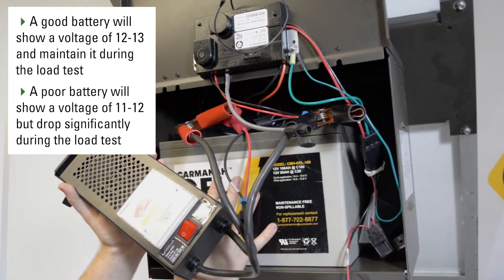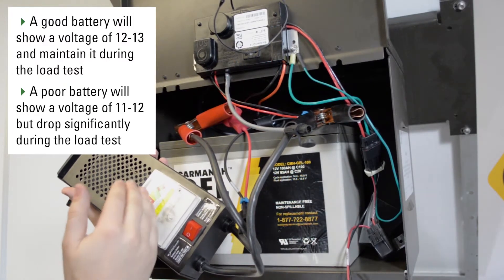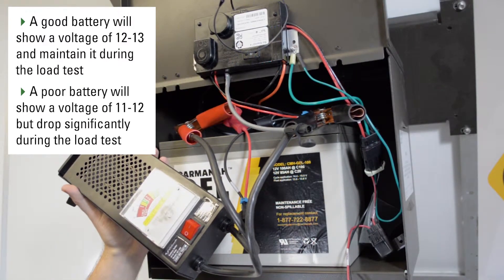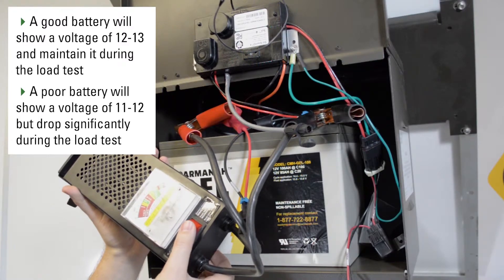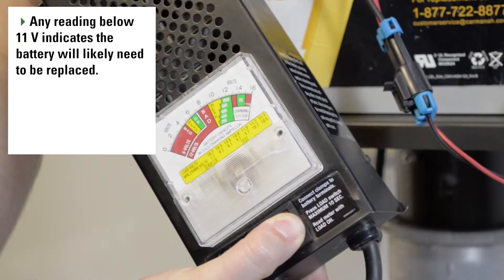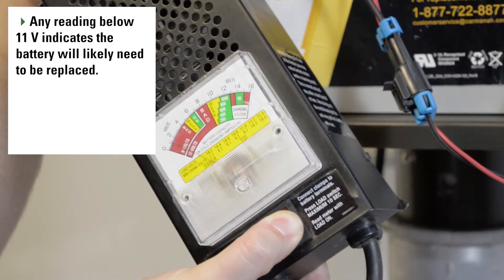If the battery had reached the end of its serviceable life, the initial voltage may be between 11 and 12. But when we push the test button, the voltage would drop significantly and continue to drop. This means that the battery can no longer store any energy.